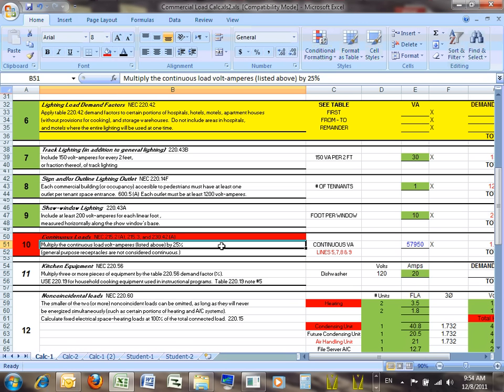While you guys are grabbing the project sheet, page 11, if you look at the electrical service, from the main distribution panel, we're going to have a lighting panel, a receptacle panel, a UPS panel, and at the same time, item 1.10 DD, you're going to have the air handling unit from the main, the cooling unit, the boiler pump, boiler 2, an auto transfer switch for the generator, and provide distribution to feed future lighting and future circuits for the future panels. Can you guys see that, everybody? I'm reading from page 11, circled, the bottom, 1.10 electrical service. That will help you. Without this, I have no idea what's going to be fed from what. If I see a lighting panel, everybody knows what's going to be fed from it. Of course, lights. Receptacle panel, of course, receptacles. Right? Main panel.